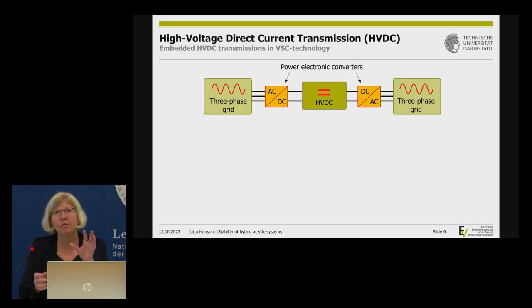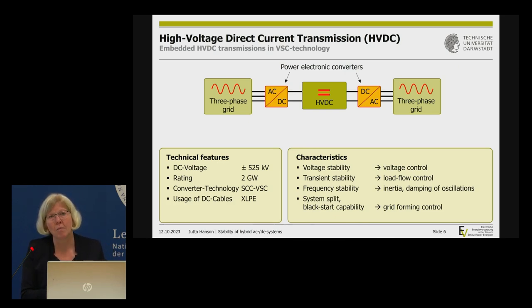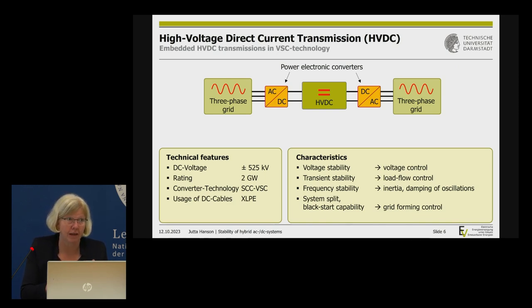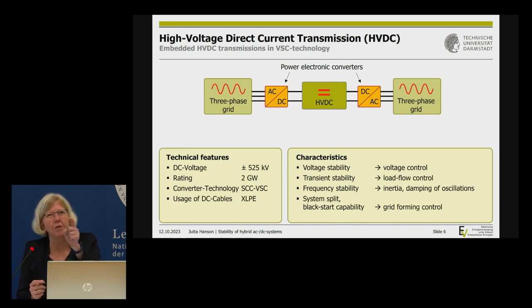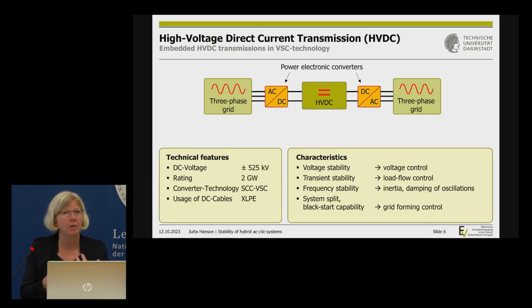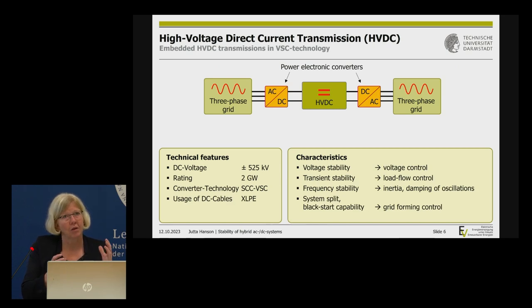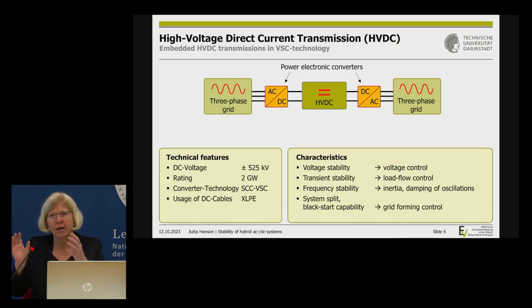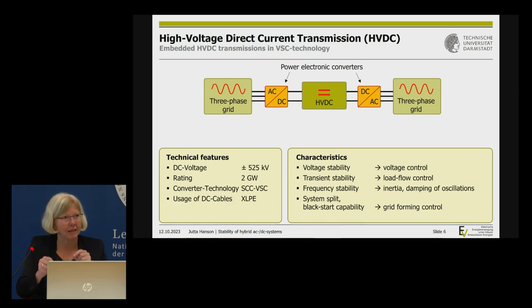The converter technology provides many degrees of freedom for stability management: voltage stability, transient stability, frequency stability. What is particularly notable is the capability for black start — the HVDC can start operation when there's nothing around, building islands. In Germany we've experienced more system splits in recent years, and it's reassuring to have technology that can help recover from such events.